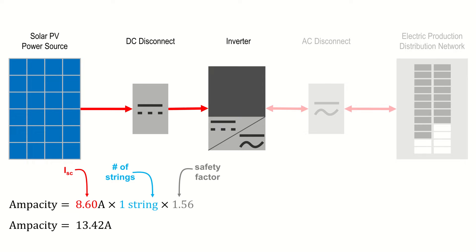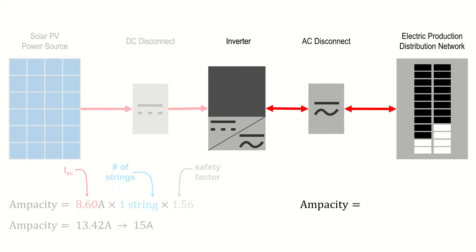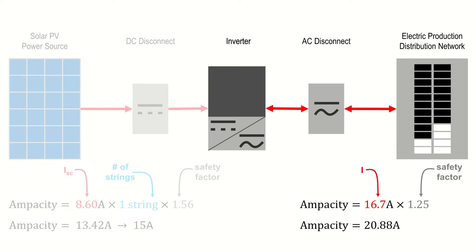As you can see in this example, we have an ampacity of 13.42 amps, so we would need to select a 15 amp fuse. The ampacity calculation changes on the AC side of the circuit. In that case, we'd use the maximum or continuous output current for the inverter and multiply that by 1.25. If, for instance, your inverter has a current output of 16.7 amps, then you would simply multiply by 1.25, yielding an ampacity value of 20.88 amps. In this case, we'd need to select a 25 amp fuse on the AC output side. For the AC disconnect itself, you'd likely choose a 30 amp two-pole model. If your inverter was transformerless, then you'd likely select a 3-pole model in order to fuse the neutral conductor.